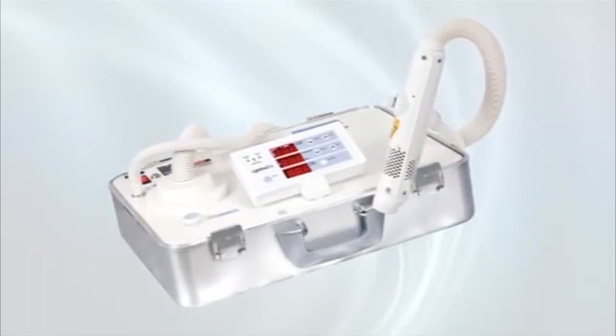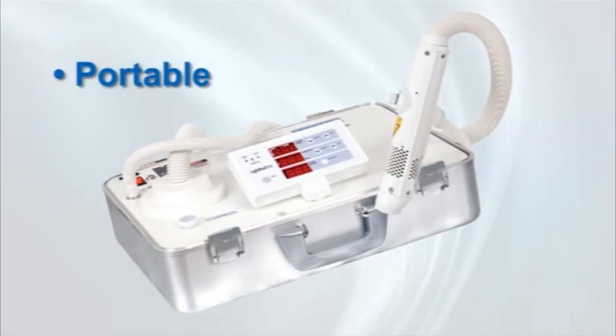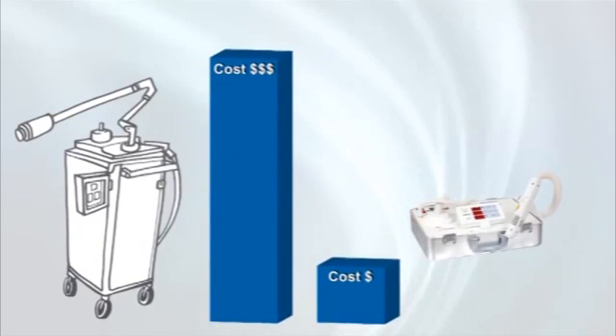There are several major benefits to this technology advancement. The first, and most obvious, is the significant reduction in size of the machine, enabling it to fit into very small treatment rooms and to be truly portable at 22 pounds in weight. Second is the savings in cost, hassle, and machine downtime associated with breakdowns and repairs of water pipes and optical fibers.